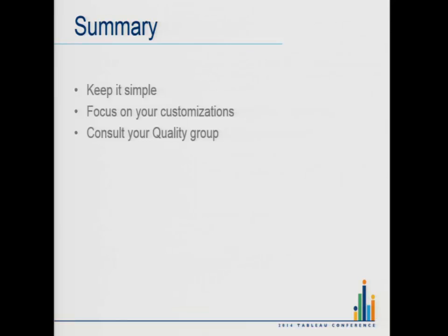Once the testing is done, we'll write a summary report with any deviations or corrective actions that were taken within the test protocols, and then circulate it for signature, and then that becomes a document that's available for any FDA audit or customer audit, for that matter, if they want to see it.